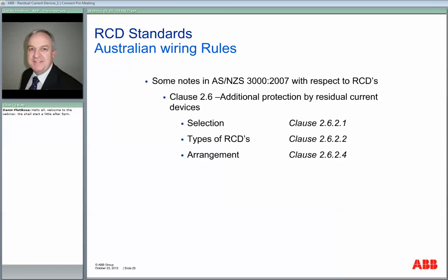One more question: what are the tests made on an RCCB to use it as an isolator? Check the parameters of the device that you're looking at. They are, by their definition, a residual current circuit breaker, so they can be used for isolation, but bear in mind they don't offer thermal or short circuit protection, because that's the operation of a circuit breaker. But you could use them for isolation purposes.